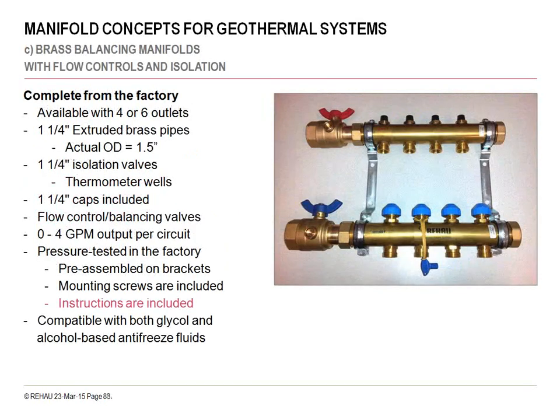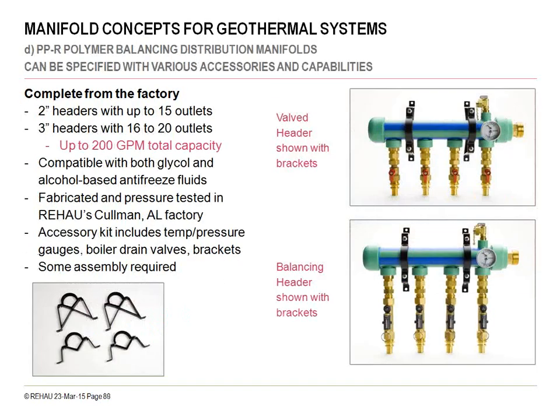RAUGEO is a proponent of having access and control of the borehole field. And access meaning being able to get to balancing manifolds, and control meaning having balancing manifolds with the ability to isolate down to a single circuit. And a single circuit could be just a U-bend in a borehole, which is generally done with residential applications, or a circuit could be representative of a borehole itself by utilizing 2 branch tees at each borehole, and we'll talk a little bit more about that. But this is more of a commercial grade header.